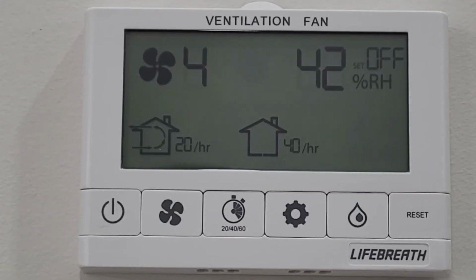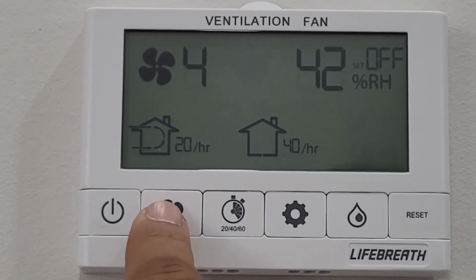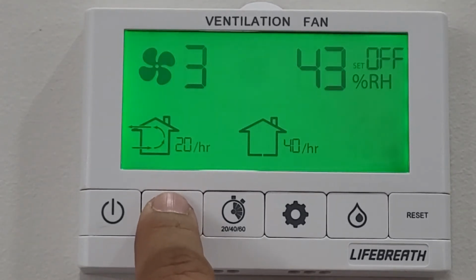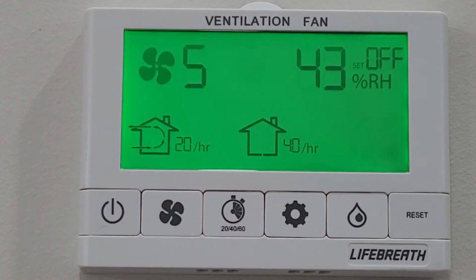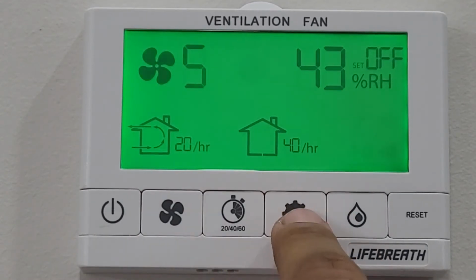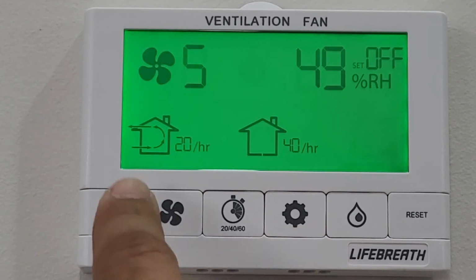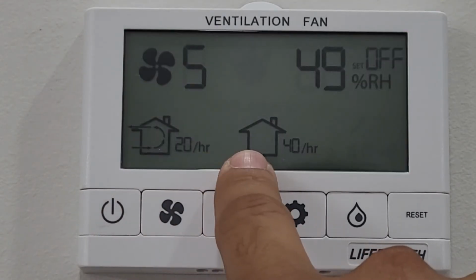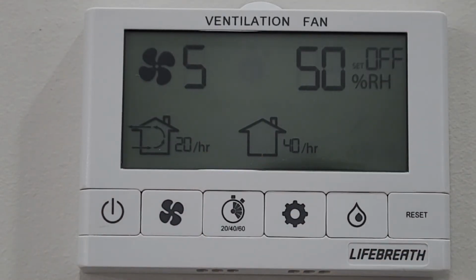So the recommended setting for HRV with your AC on is that first your fan speed can be between 3 to 5. And then for the ventilation, so automatic ventilation mode on, you can have 20 minutes on, 40 minutes standby option. So this will keep your house enough ventilated. As with AC, we keep doors and windows closed, so your ventilation must be properly done.